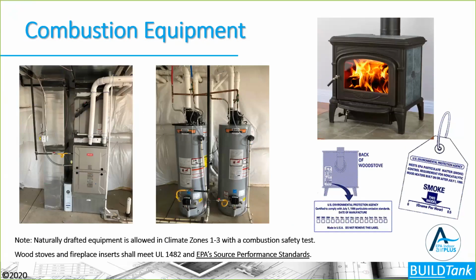Combustion equipment, there's an example of the sealed combustion furnace, a direct vented water heater. And the direct vented water heater, you see at the very bottom, that's the combustion chamber. It's open to the house, so it's not sealed combustion, but it does, again, have that safety mechanism. So wherever it tries to backdraft, then it turns off the system here. Stoves, again, and fireplaces, it doesn't necessarily preclude the ability to use wood-burning stoves and fireplaces, but you need to follow these standards and guidelines that are in the construction specifications.